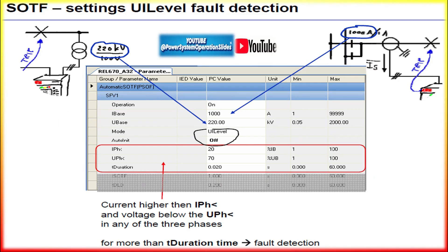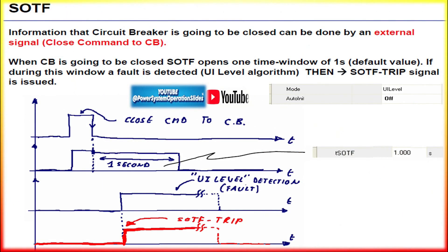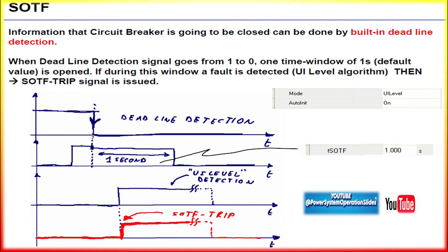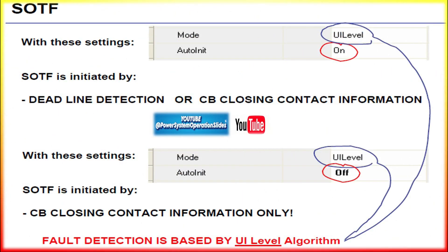To delve deeper into the SOTF function and its relevance to distance protection, let's examine more intricate technical aspects — focusing on operational challenges, relay configuration, and coordination with other protection schemes. When a fault exists on a transmission line but the breaker is open, the relay's normal distance protection using impedance measurement may not be able to detect this fault until current flows through the line. The SOTF feature becomes essential when the circuit breaker closes onto a faulted line. Upon closing the breaker, in the pre-fault condition when the breaker is open, there is typically little to no voltage across the open breaker terminals, as the fault effectively shorts the line. This low voltage condition is detected by the relay.